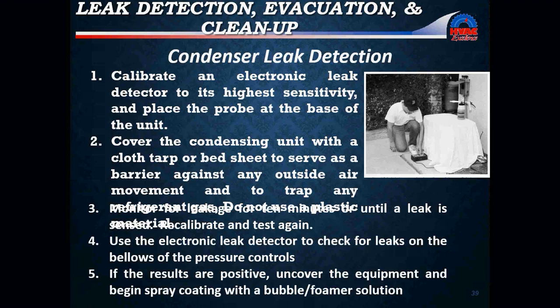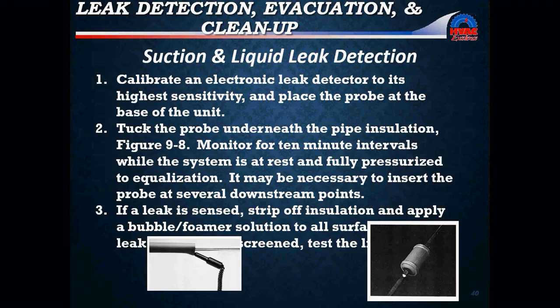Okay, it could be a minute little leak. It could be an actual pinhole where it actually leaked all the oil out. But you have to look at your areas of where these things may be. If you have suction and liquid line leaks, you're going to do the exact same thing.